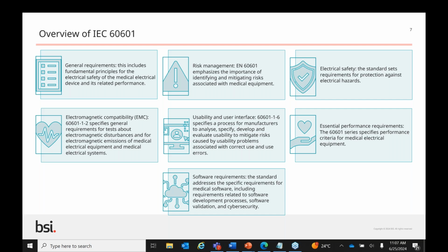It covers software requirements. So the standard also outlines specific requirements for medical software, encompassing software development processes, software validation, and cybersecurity. Electrical safety, so this can cover aspects such as insulation, earthing, leakage currents, electrical connections, protection against electric shock as well. And lastly, essential performance. So this criteria may vary depending on the specific type of device and its intended use, such as accuracy, measurement range, response time, or alarm functions. Next slide, please.